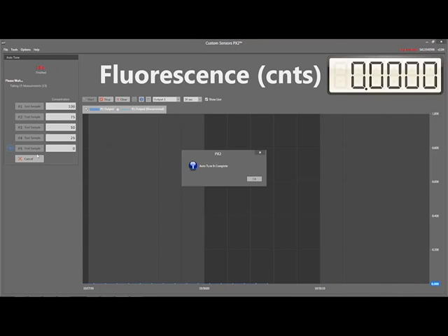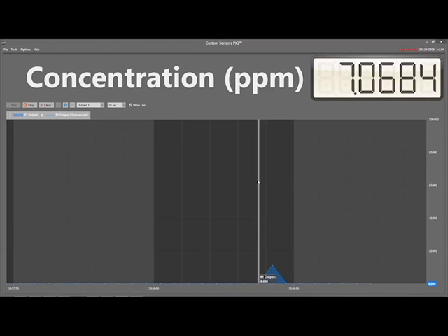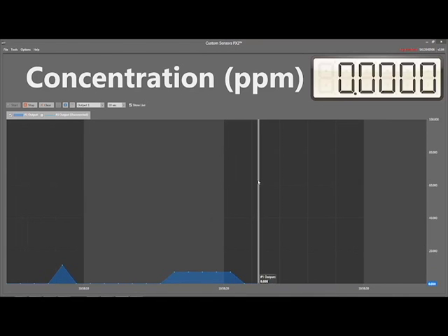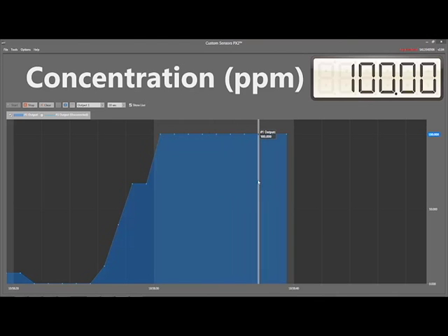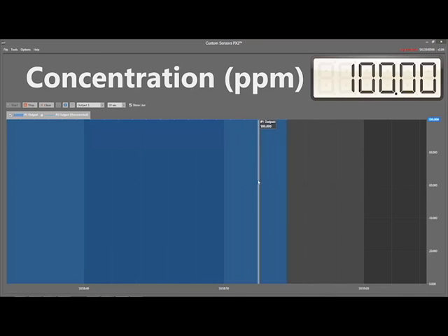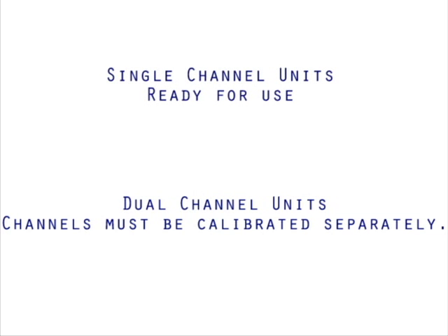Once the PX2 finishes measuring sample number 5, a notification will pop up alerting me that auto-tune has completed. The chart will automatically update to reflect the calibrated scale, and the units of measurement above the graph will also change. If the unit is configured to make a single channel measurement, it is now ready to be used. For dual channel absorbance or fluorescence units, the second channel must be calibrated separately. To do this, go to the Tools drop-down in the menu bar and select Channel number 2 Auto-Tune, and repeat the same process with the second sample set.